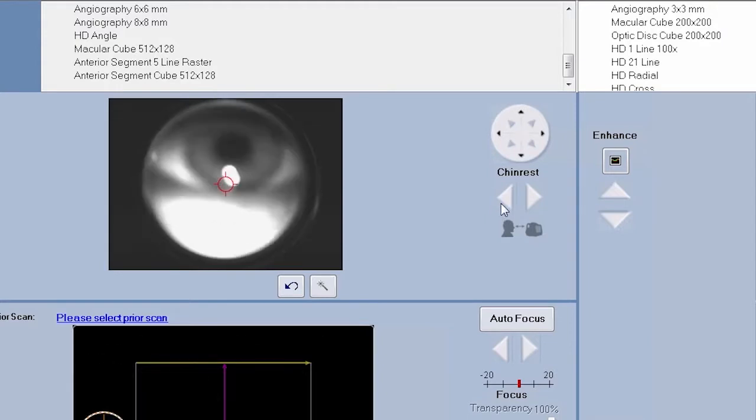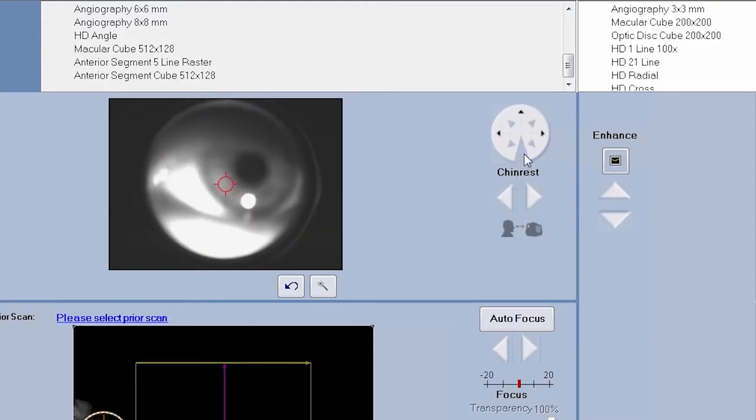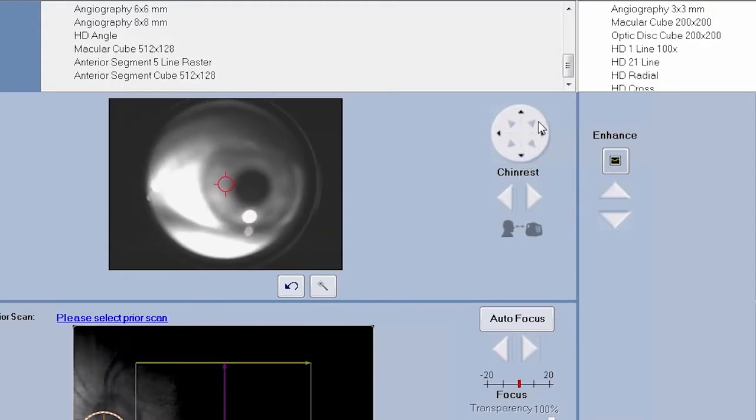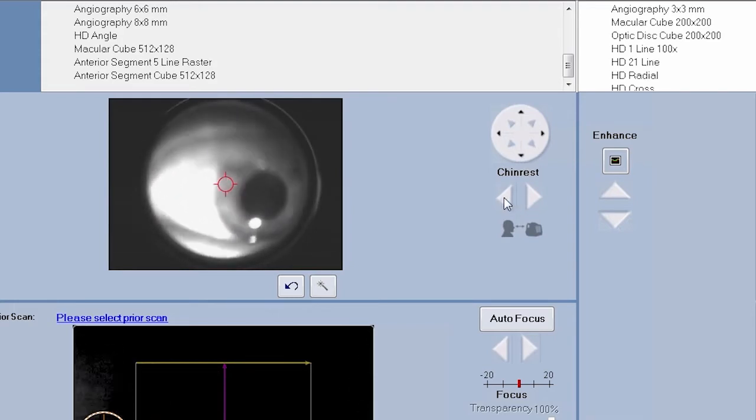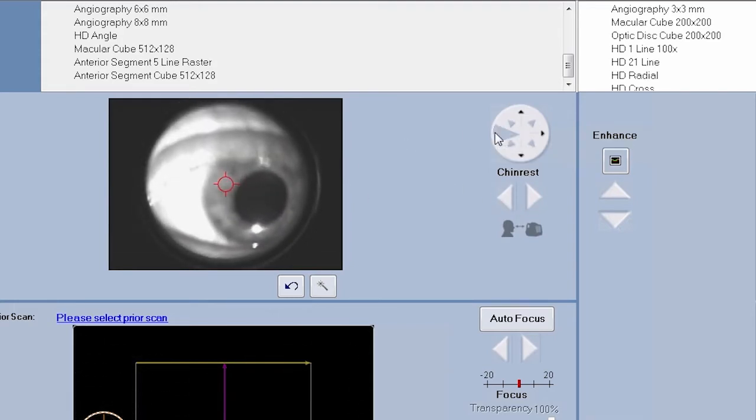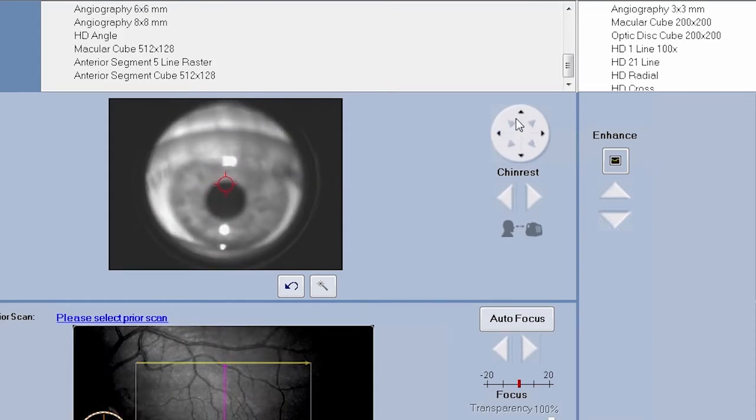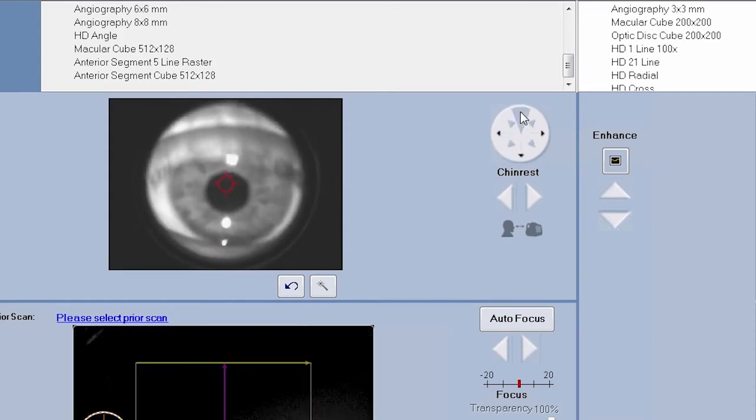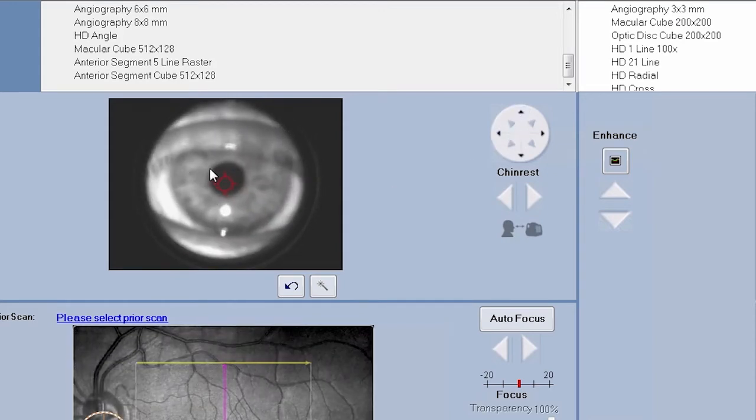Focus the iris by adjusting the chin rest position using the triangular buttons on the chin rest controls. This will move the patient toward or away from the camera lens. Move the patient closer to the lens and make small adjustments until the iris is focused.